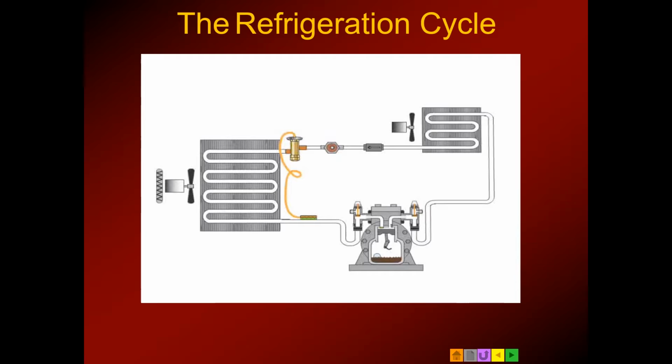So basically you've got your return air coming across your evaporator and it boils off the refrigerant. When all that refrigerant is boiled off or vaporized, it's now a saturated vapor. That low pressure vapor is then returned to the compressor and the process starts all over.